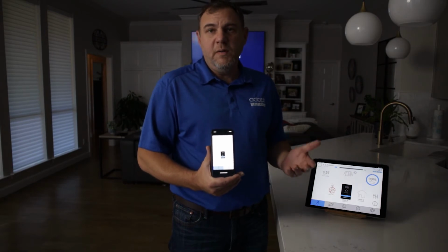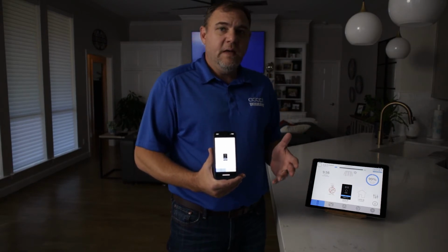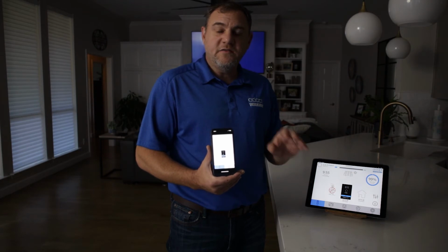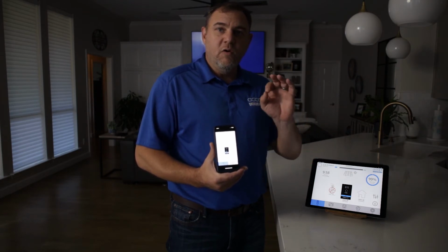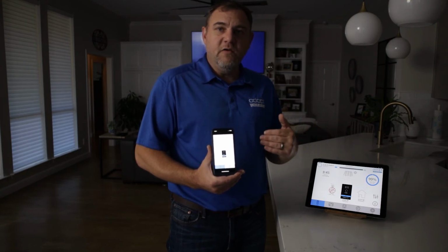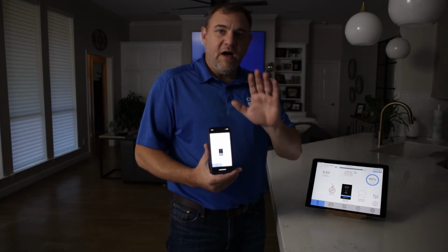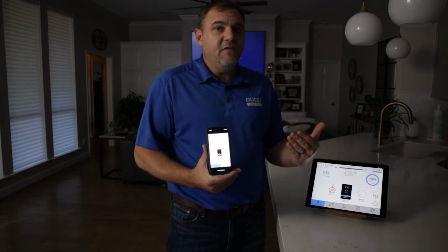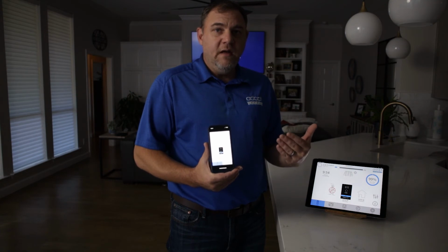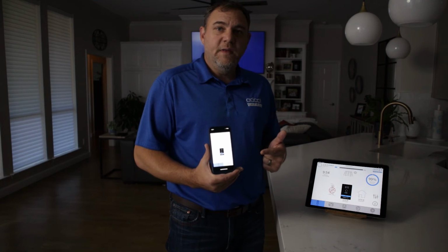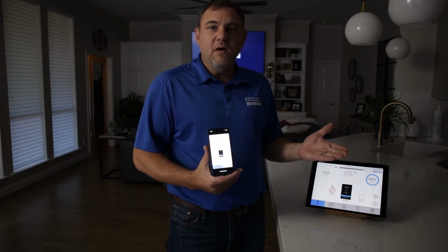However, we actually brought grid power back about 4 minutes ago. And the reason why we don't have power yet is because the Sonnen battery is doing a grid check. It's got to check the grid for good power, basically within spec power coming into the home, and it's got to watch the grid for 5 minutes straight for perfect power. If at maybe 2 minutes and 30 seconds of it watching the grid, it sees a power blip or something like that, it's going to restart that timer. We probably won't have that happen here.